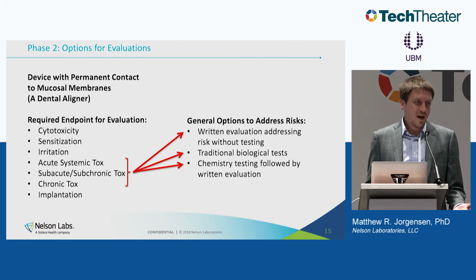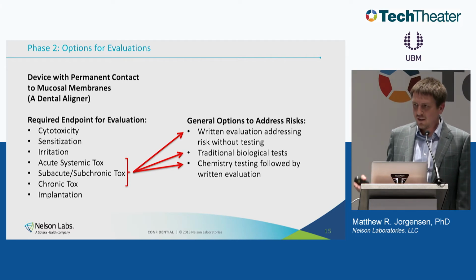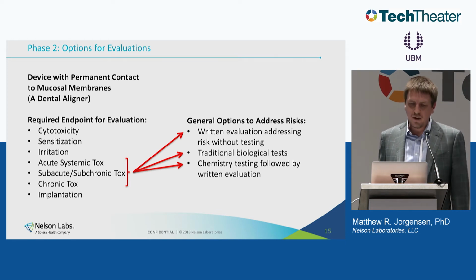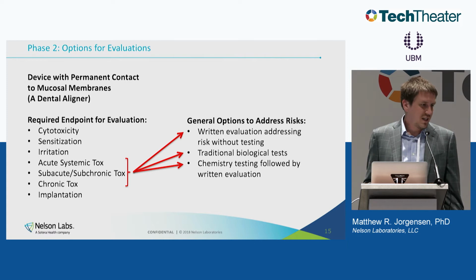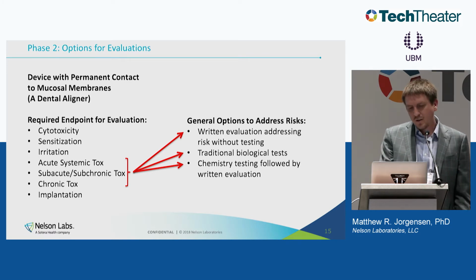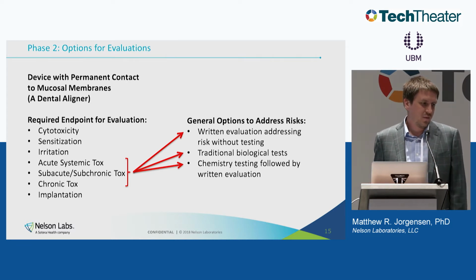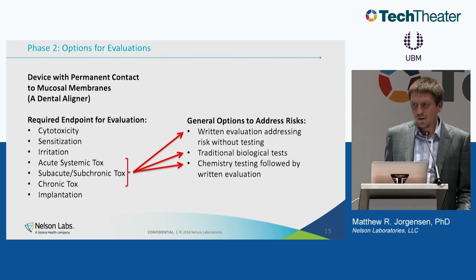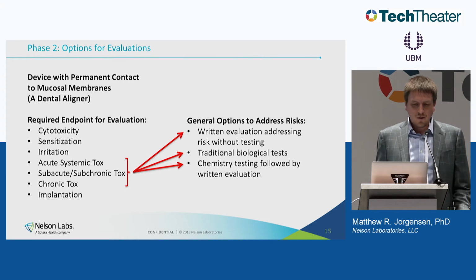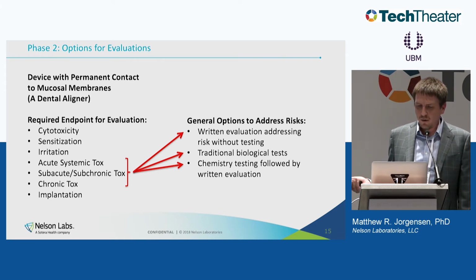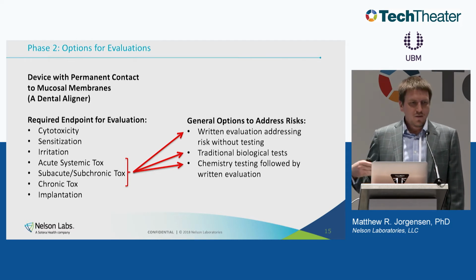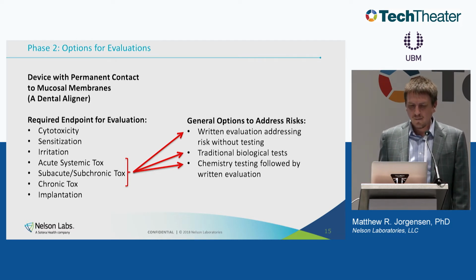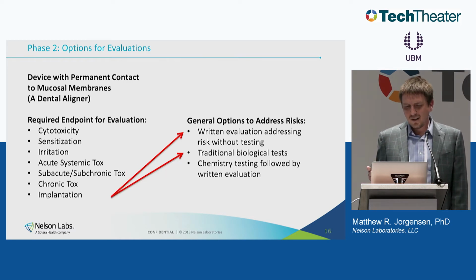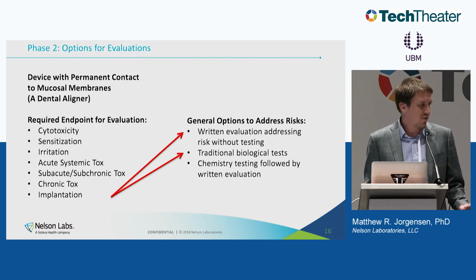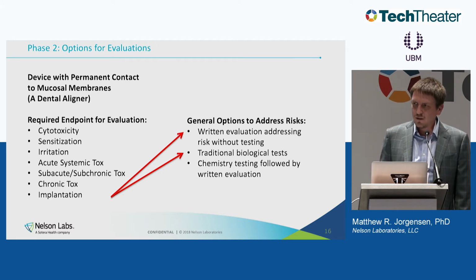Then for the remaining systemic toxicities, really any of these could work. If you have a very common material, it's the same argument as before. You can do the traditional testing, though I can say that acute systemic's not that bad, but subacute and subchronic testing together with chronic tox is a pretty expensive, long endeavor. You're looking at at least $100,000 and a few months. So we try to avoid that if we can. So what we would recommend by default is chemistry testing, followed by some sort of toxicological risk assessment in this case. And then here, for something like a dental aligner, I'm sure that we would recommend just having a written evaluation based off of the material and how it's used.